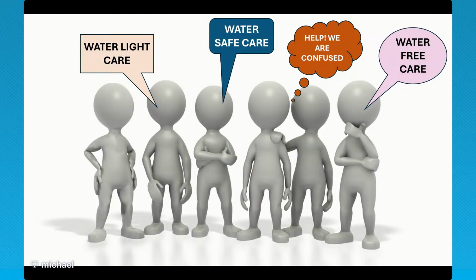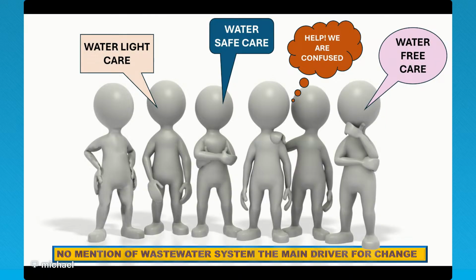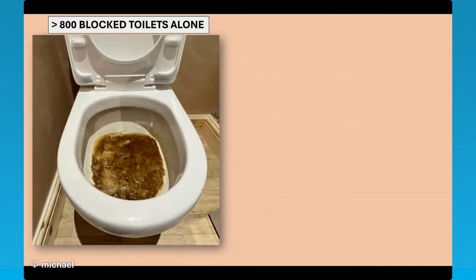Because our standard infection control precautions are not very effective in preventing transmission from water and wastewater systems, we've had to remove water services. This has produced confusing nomenclature, such as water-free care. Some people think there's no water on the unit. There's no mention of the wastewater system, which is really the main driver for change. So people don't tend to look at wastewater systems.